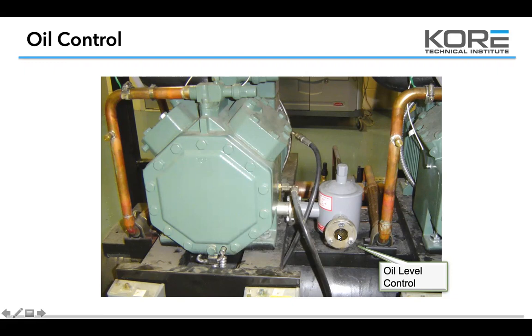That's why we have a hard time telling the difference between liquid and oil — POE runs really light and can be mistaken for liquid. Just put your hand on the front of that compressor. If refrigerant's boiling off, that front is going to be cold. There's your valve plate — if that discharge line is anywhere cool, you're getting liquid into the system.